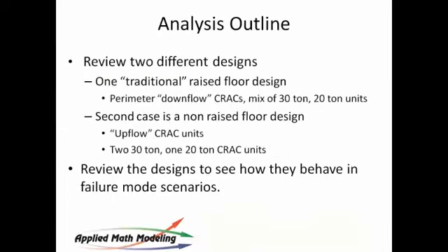Okay. So what Magnus and I are going to do today is take a look at two different designs, and what we're going to be focusing on is this whole issue of N+1. N+1, of course, is the idea that you have enough cooling capacity to be able to handle a failure mode situation or a maintenance situation where one of the cooling units in the room goes down and you're left with the remainder, and you have to understand what's going to happen in that case.